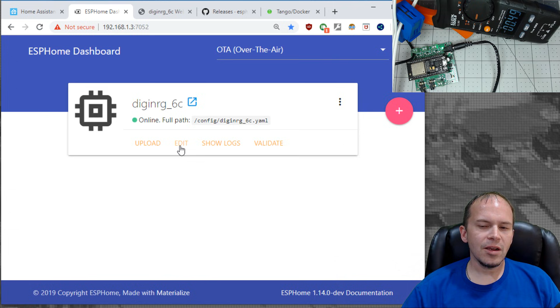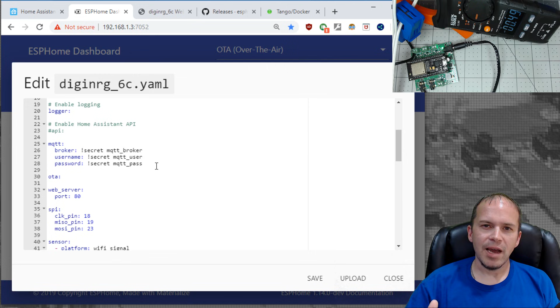Now, of course, the bigger load you put on it, the more accurate it's going to be. For instance, if you have a 50 amp clamp, and there's a way you can put, say, a 10 or 15 amp constant load on it, you could get a much more precise calibration. So we'll change this to 14,500 and upload it. You'll see now that puts us at 0.47, pretty close. Now I did calibrate some of these clamps using about a 10 to 11 amp load, and it got me a little more precision like I spoke of, even with the light bulb. So we'll set this one to 15,420, save it and do an upload.